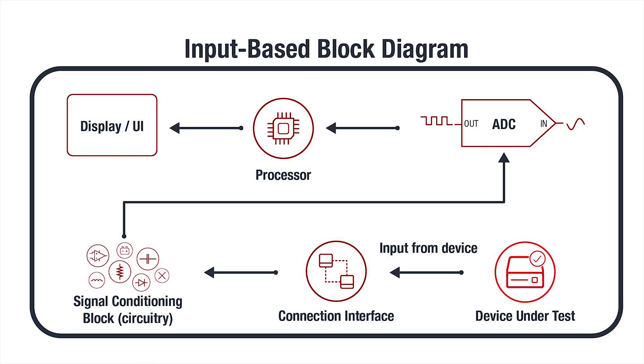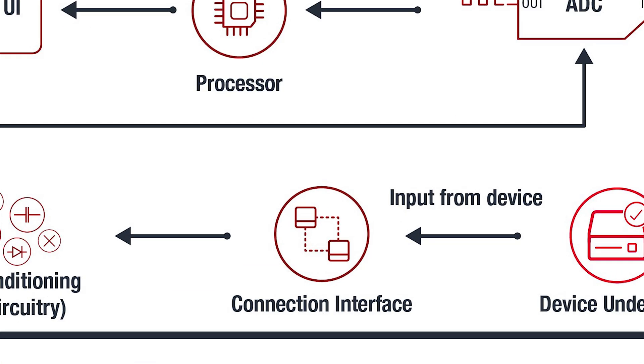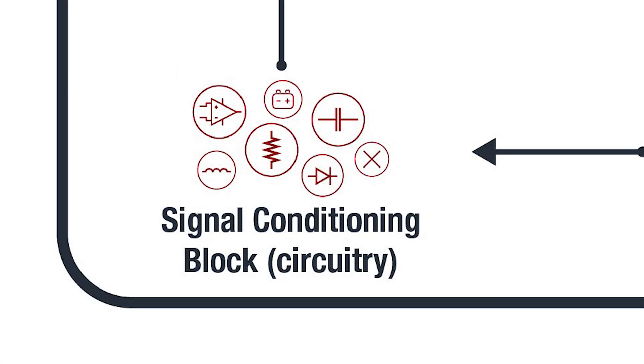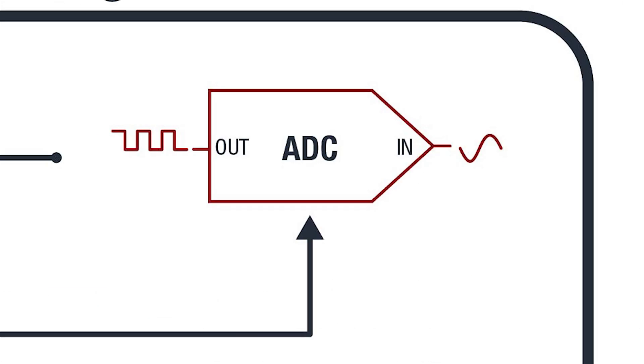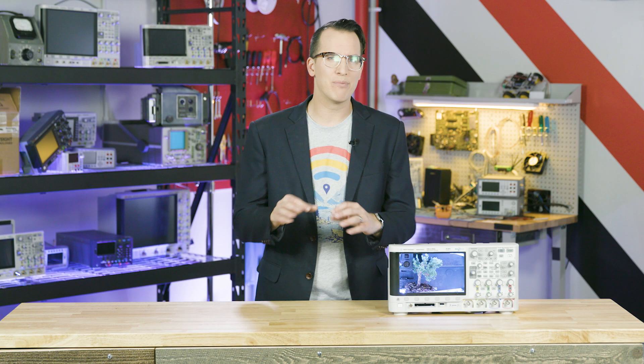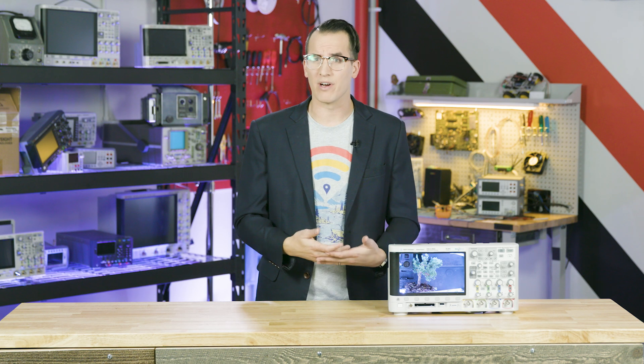To recap, input-based test gear has a connection interface, a signal conditioner, an ADC, a processor, and a data readout. That's how input-based equipment works.